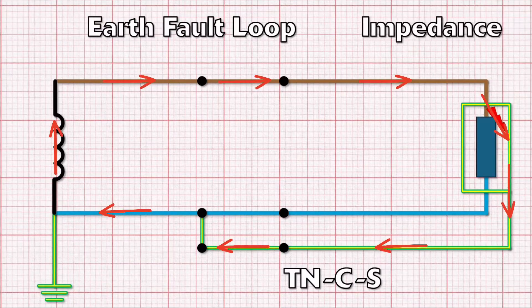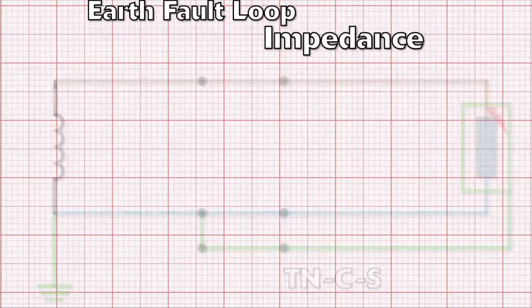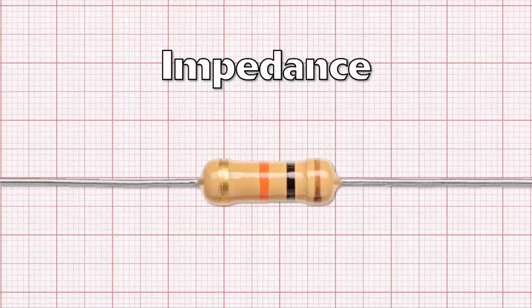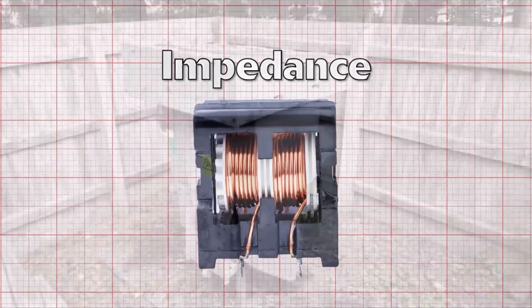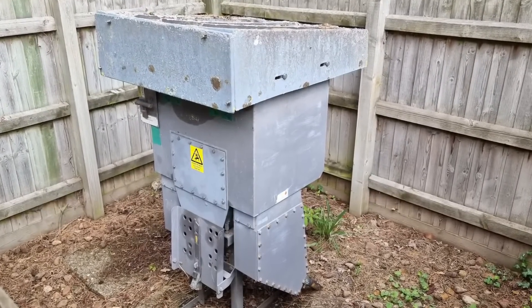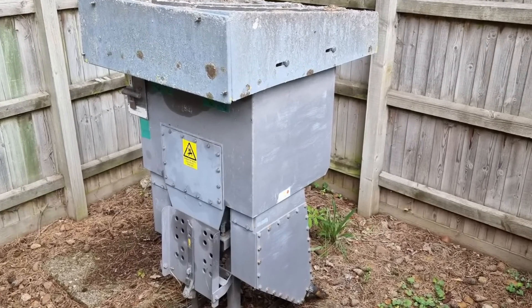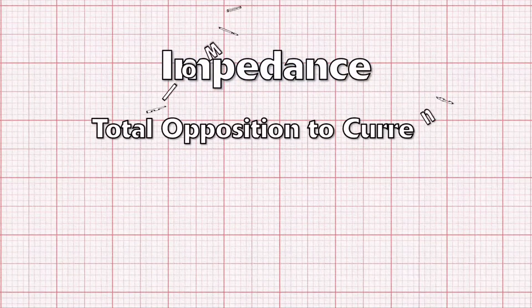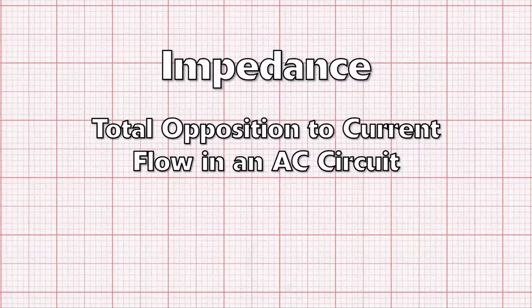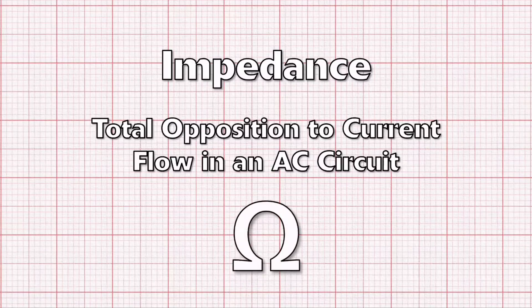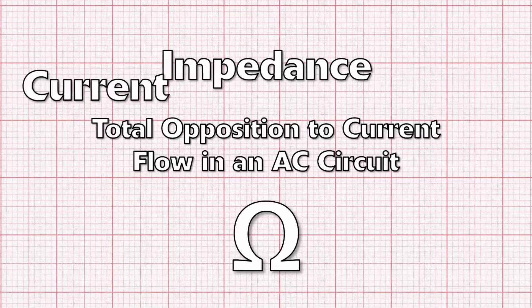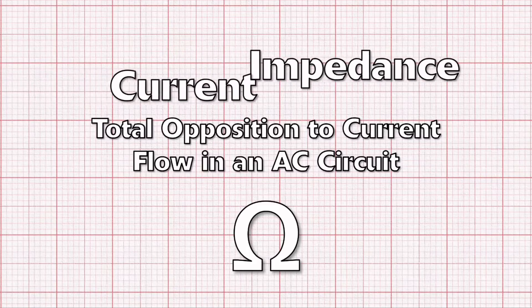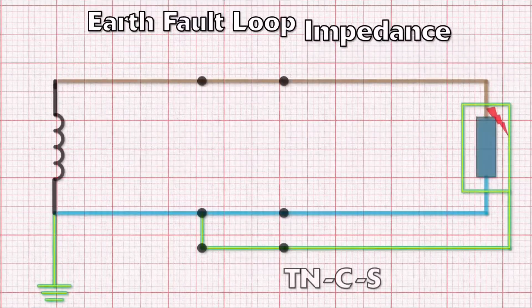What about the 'impedance' part? Impedance is just another type of opposition to current flow. It's similar to resistance but takes into account the extra opposition caused by coils in AC circuits. Because the transformer feeding the property is a large coil, it adds opposition in the form of inductive reactance. Impedance is the total opposition to current flow in an AC circuit, measured in ohms, and it largely acts to stop the current from flowing.